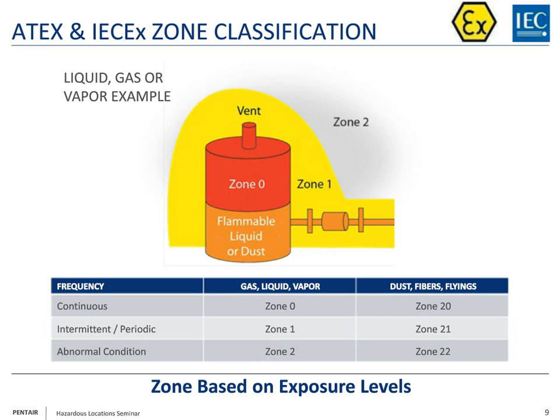Now we switch gears. Now we think about the international standards outside the United States. You look at ATEX and IECEx zone classification system. What these standards do is they break things into zone 0, 1, and 2, and those are for gas, liquids, and vapors. Again, thinking about oil and gas, petrochemical applications. And then they break things into zone 20, 21, and 22 for dust, fibers, and flyings. It's a little different in terms of how they break them up into three different zones.